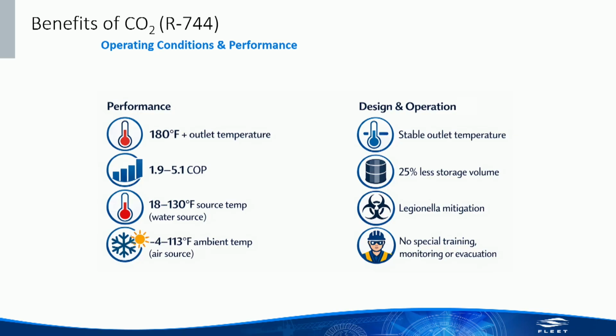On the source temperature side, we can accept a pretty wide range. From a GEO or water source perspective, we can see as low as 18 degrees source water all the way up to about 130 degrees, still operating at full capacity with very minimal hits on COP and reliability. For the air source variants, you can go down to -4, truthfully probably similar to or lower than Mitsubishi - it's more a restriction of air chambers and testing facilities to see how low we can push it.